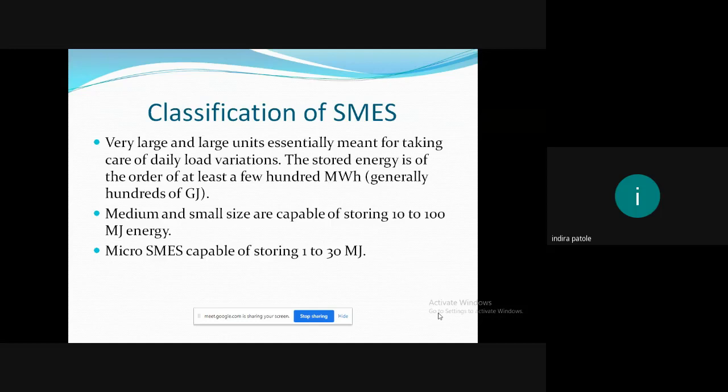Units of the second classification is medium and small size, which are capable of storing energy of 10 to 100 megajoules. These units are useful for stabilizing the power system against the low frequency oscillations and also to support a generating plant for a few seconds or minutes. In case one generator out of several generators which are working for the plant fails, you can use the SMES unit. Then the third classification is of micro SMES capable of storing 1 to 30 megajoules of energy. These can be used for supplying critical loads during voltage sags and total power interruptions lasting for only a few seconds. When used as UPS, it is capable of supplying megawatt of power for durations of order of a few seconds. So, typically a kilowatt, one kilowatt hour unit, that is 3.6 megajoules can support 1.2 megawatt of load for 3 seconds.